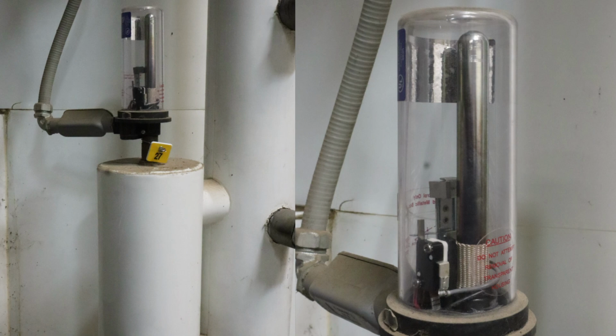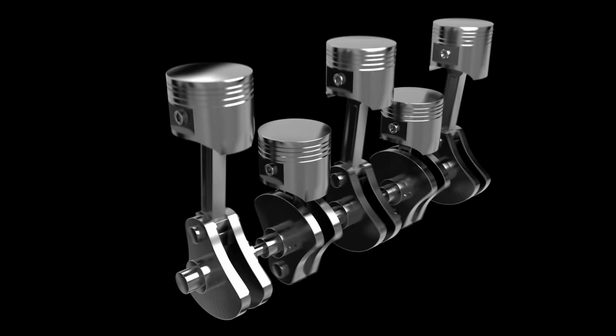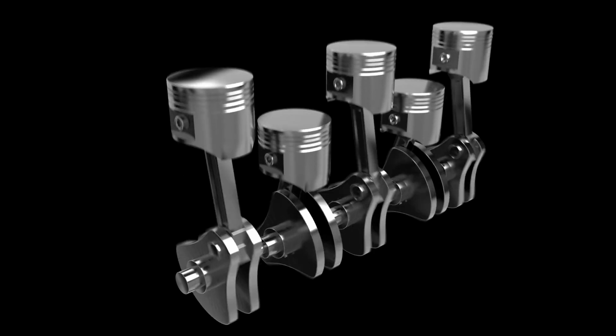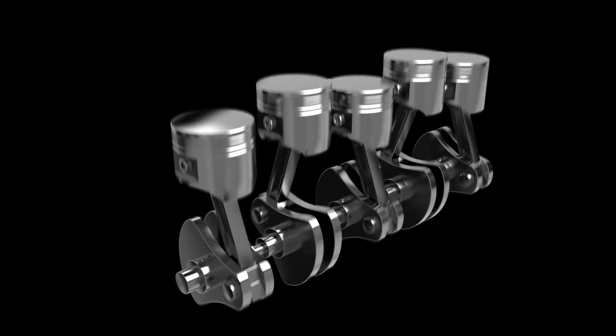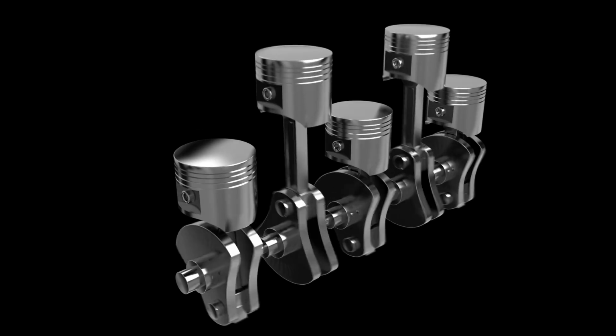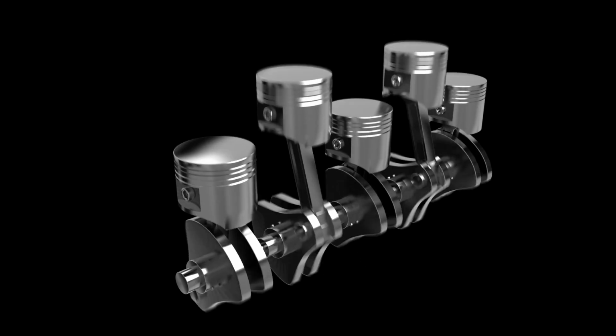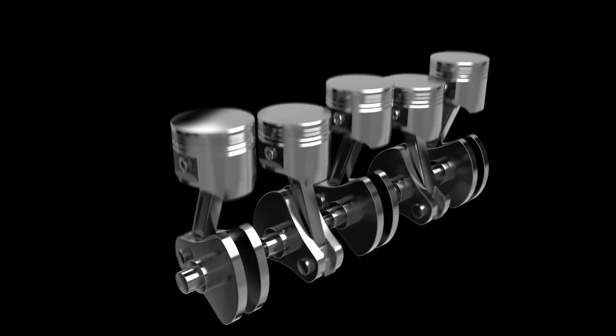Slugging can be caused by a high liquid level in the supplying vessel, such as a suction accumulator. Slugging can also be caused by a rapid drop in suction pressure, resulting in liquid carryover. Regardless of the cause, slugging will have devastating mechanical effects on a compressor, especially a reciprocating compressor.